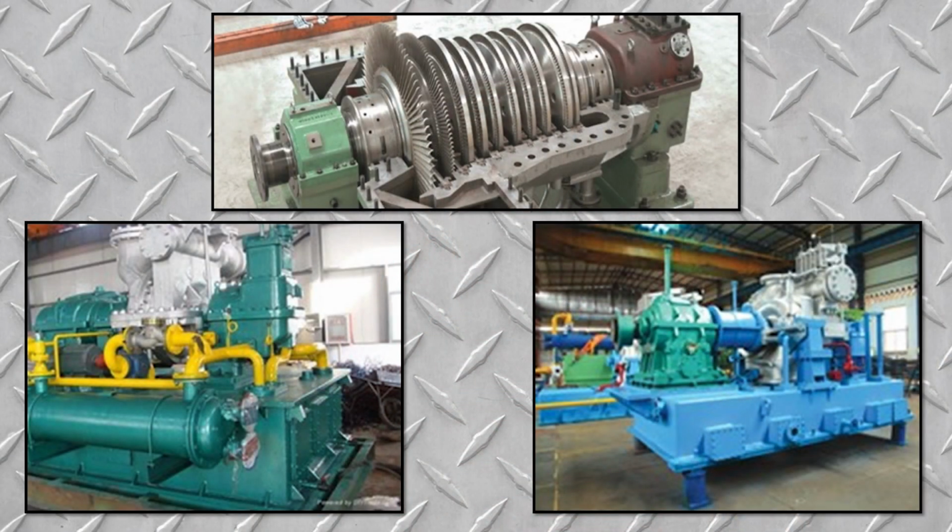If you do have a lot of flow going to a second pressure, often you'll see people stick in an actual back pressure turbine. A back pressure turbine is a way of making electricity through that pressure drop. And in fact, these devices are common enough that companies that make these back pressure turbines build to an inventory. So you can just call them up and say, ship me one of those 50 kW units, something like that.